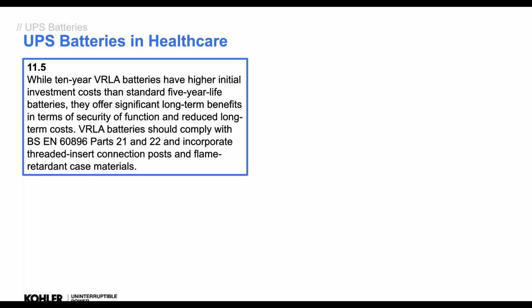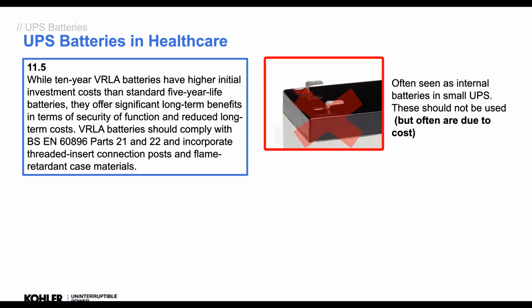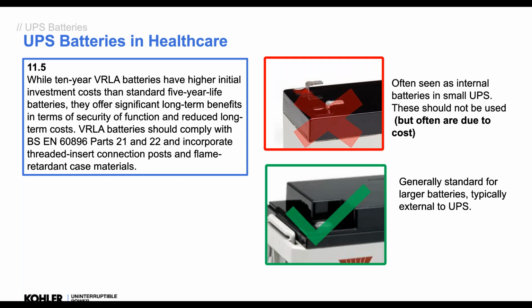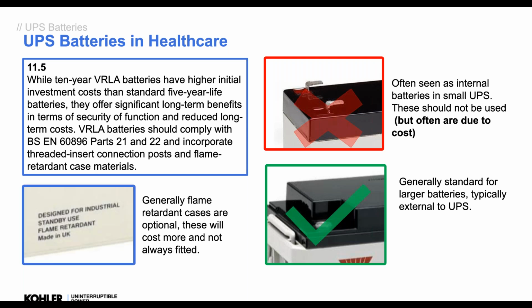so HTM tends to grow towards the 10-year valve regulated lead acid battery. It is a good option for a standby battery. 10-year doesn't cost a lot more than 5-year, but you should be specifying it, okay? And it has to comply with the requirements, okay? But it also specifies things like you cannot use push-ons. You know, it has to be a threaded insert type battery. So this typically means a larger battery, okay? And it should also be flame retardant, okay?